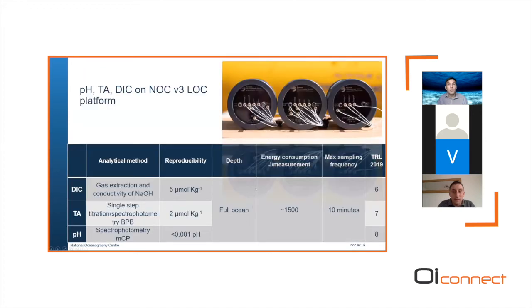We've also developed sensors for the carbonate system, really important for the scientific community to look at the effects of carbon dioxide dissolving in seawater. So there's a very high precision, high reproducibility pH meter. The accuracy is literally determined by the reference materials we can get hold of and the accumulation of errors in measuring those. The precision is very, very good, less than a millipH.